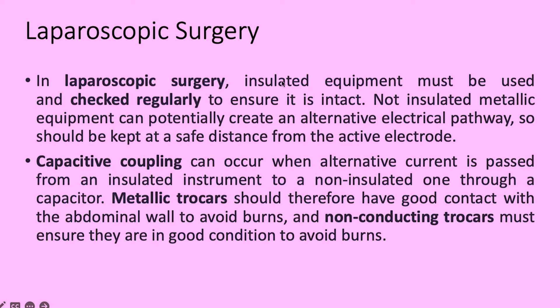In laparoscopic surgeries, insulated equipment must be used and checked regularly to ensure it is intact. Non-insulated metallic equipment can potentially create an alternative electrical pathway, so it should be kept at a safe distance from the active electrode. In capacitive coupling, when the alternative current passes from an insulated instrument to a non-insulated one, metallic trocars should have good contact with the abdominal wall to avoid burns, and non-conducting trocars must be in good condition.